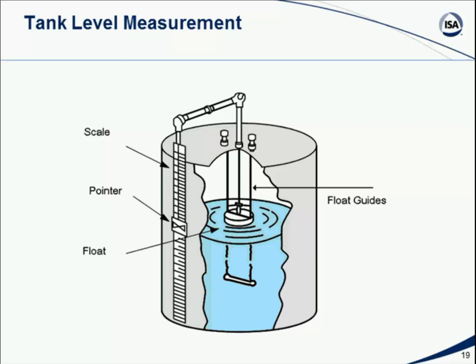The good news is that instead of having to run around and read the pointers on the sides of the tanks, these days the same kind of companies that make float tape systems can mount an encoder on the side of the tank. An encoder can be thought of as sort of a reel with a spring attachment on it, so that as the float goes up and down, this reel reels in and lets out the line, and the line has some encoding on it. Usually in the case of a tape float system, it's punch-coded punch hole values that allow me to count how many inches of tape go in and back out. And this can be converted to an electrical signal, and I can get a 4 to 20 milliamp signal sent back to a control room somewhere.